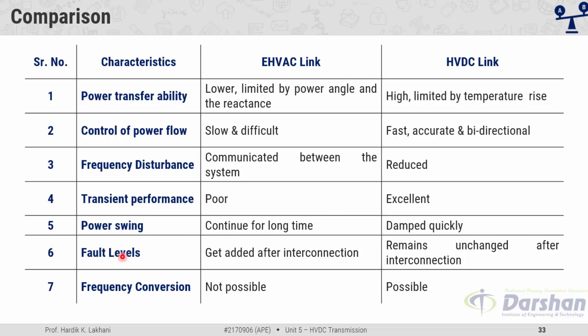Power oscillations continue for a longer time in AC systems, but are damped quickly in HVDC systems by control units. Regarding fault levels, in EHV AC links, fault levels get added after interconnection, but in HVDC links they remain unchanged. Frequency conversion is not possible in AC links, but in HVDC we can change the frequency.